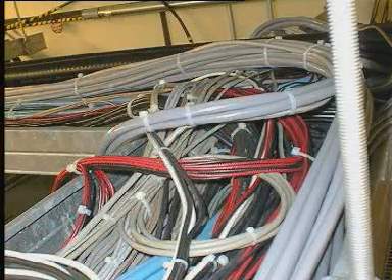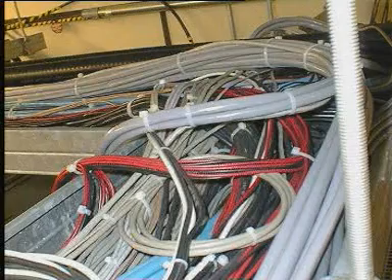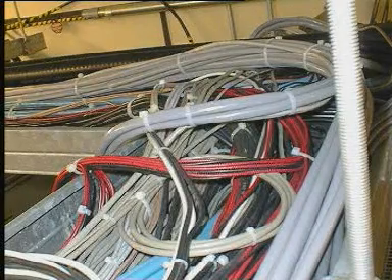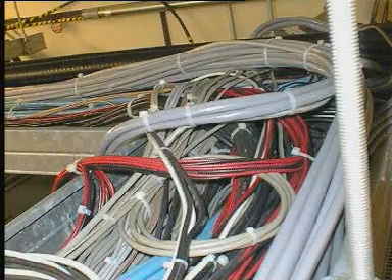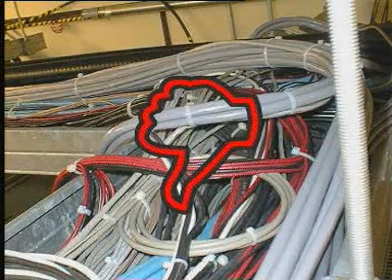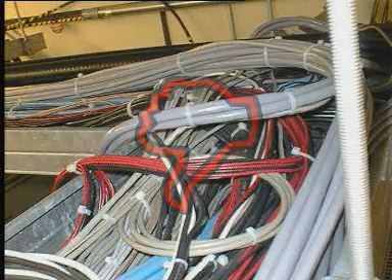Roof spaces can often hide many sins. A competent installer would never leave a cable ladder organized in this way. Power and signal cables should always be separated. They should always be neat and well secured to the cable ladder.